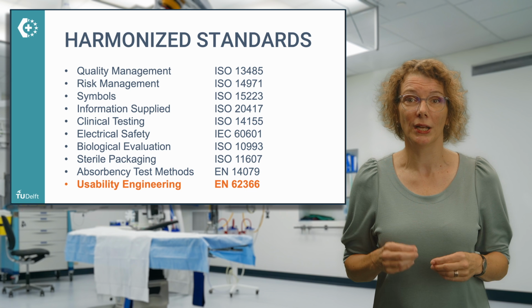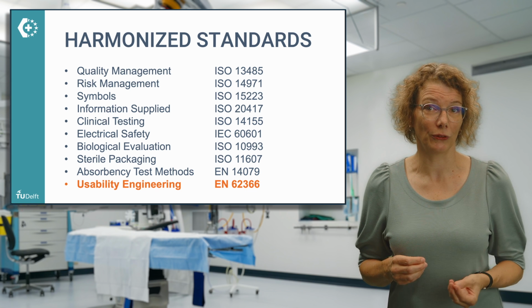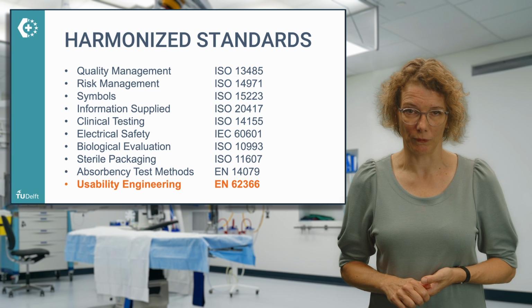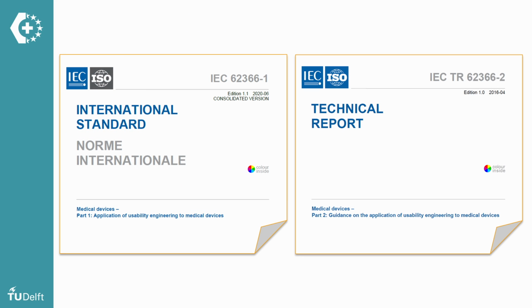However, the previous version, IEC 62366 from 2007, was harmonized with the predecessor of the MDR, the Medical Device Directive. This implies that performing usability engineering has been recognized as an appropriate process to manage use-related risks for medical devices. And also note that the MDR states that manufacturers should take the generally acknowledged state-of-the-art methods into account in their device development.